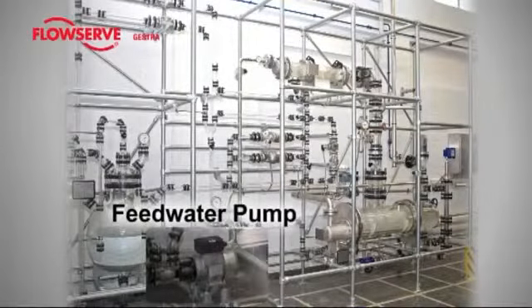This video shows the thermal processes taking place during the generation of saturated steam in a glass steam boiler. This is demonstrated with the aid of the glass evaporator built by Gestra AG, Bremen. The evaporation process occurs at an operating pressure of 1.3 bar gauge, which corresponds to 2.3 bar absolute. At this pressure, the boiling point as well as the saturation temperature are 124.7 degrees centigrade.